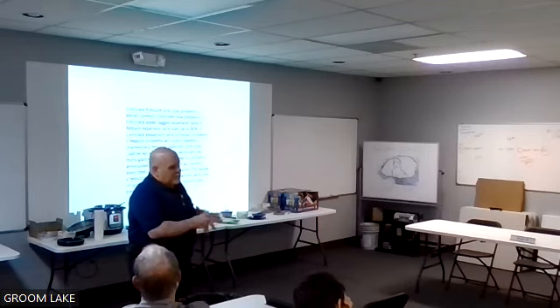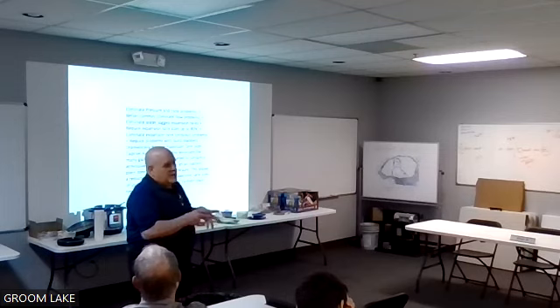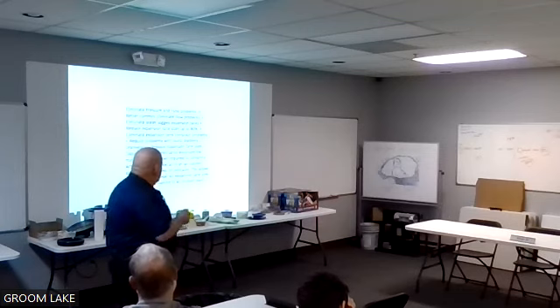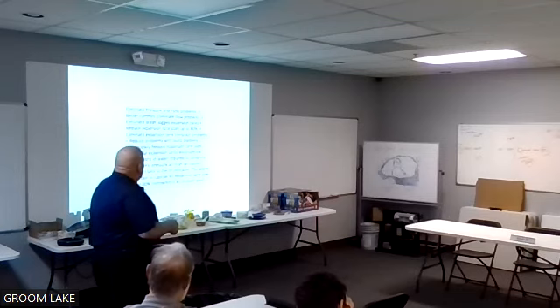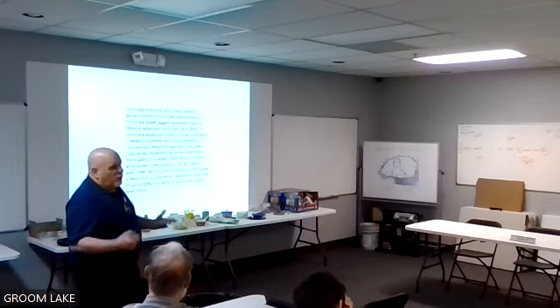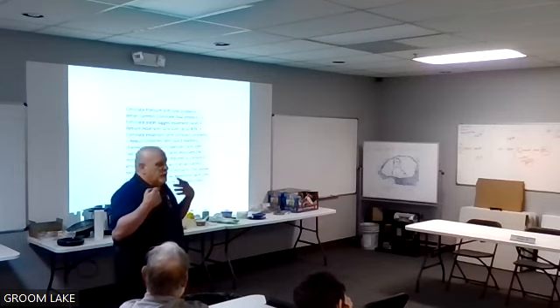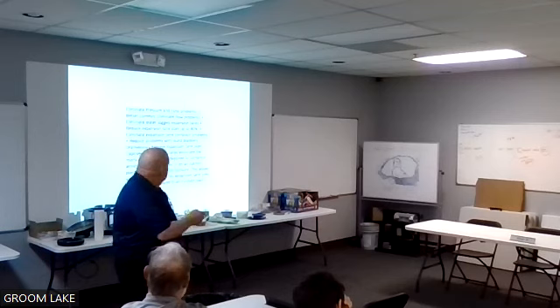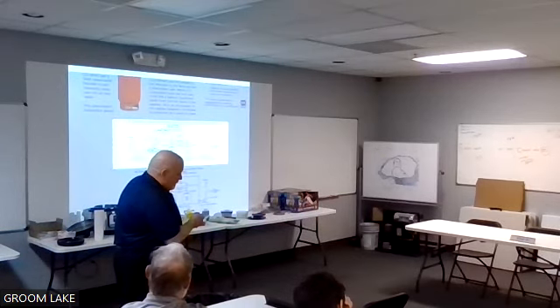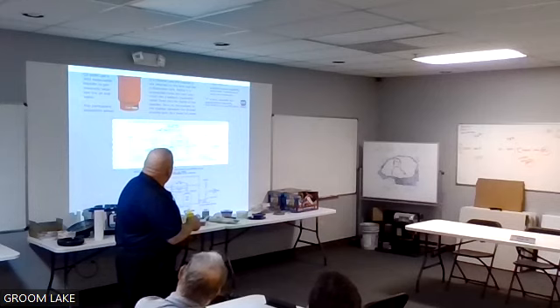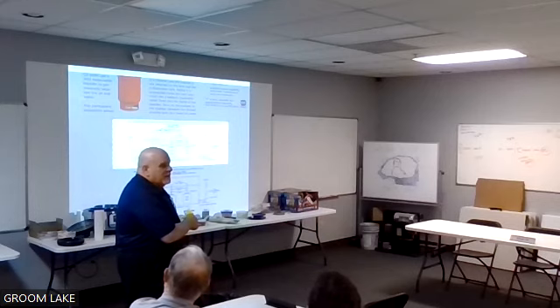They make these acceptance volume tanks. We're going to show you all these in a minute. They're less money, but you can replace the bladder in the full bladder tank. So this is just talking about the reason you want to use a bladder tank. They don't waterlog. You have an air charge, and for example, here's an install right here. There's two tanks. Here's your air vent before we come down to the tank.